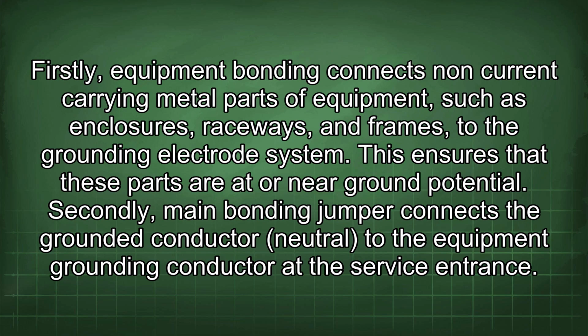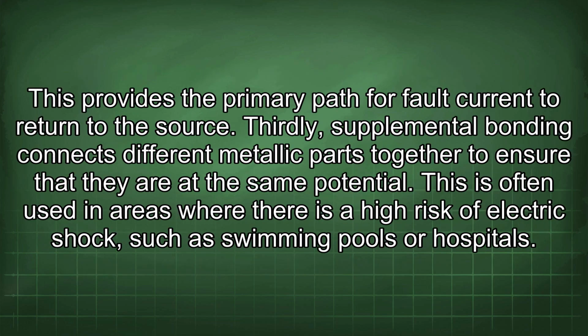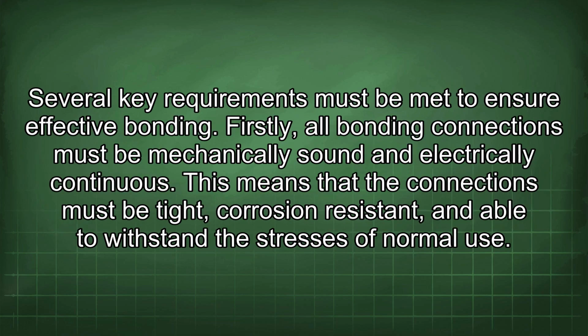Secondly, the main bonding jumper connects the grounded conductor neutral to the equipment grounding conductor at the service entrance. This provides the primary path for fault current to return to the source. Thirdly, supplemental bonding connects different metallic parts together to ensure that they are at the same potential. This is often used in areas where there is a high risk of electric shock, such as swimming pools or hospitals. Several key requirements must be met to ensure effective bonding.